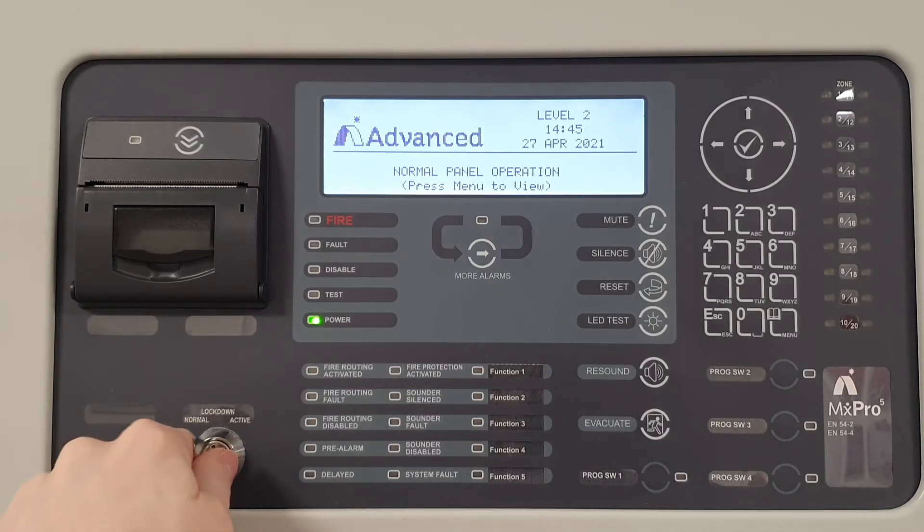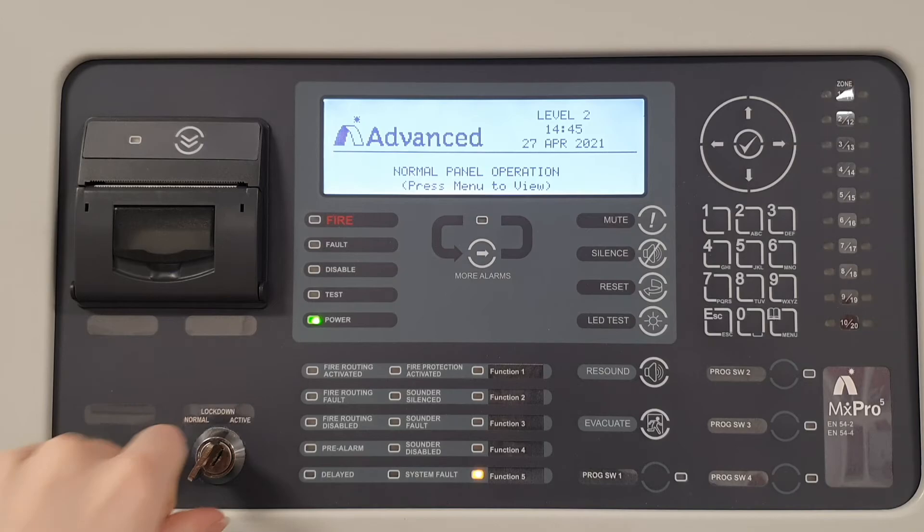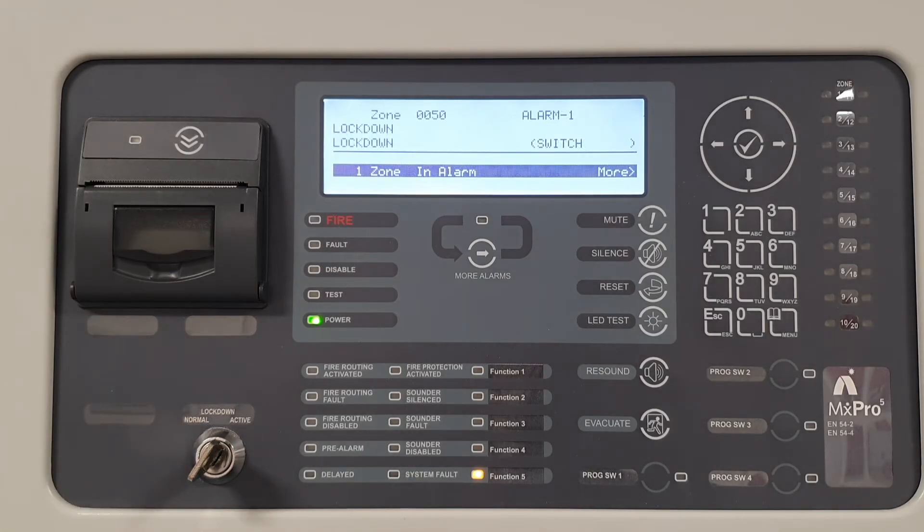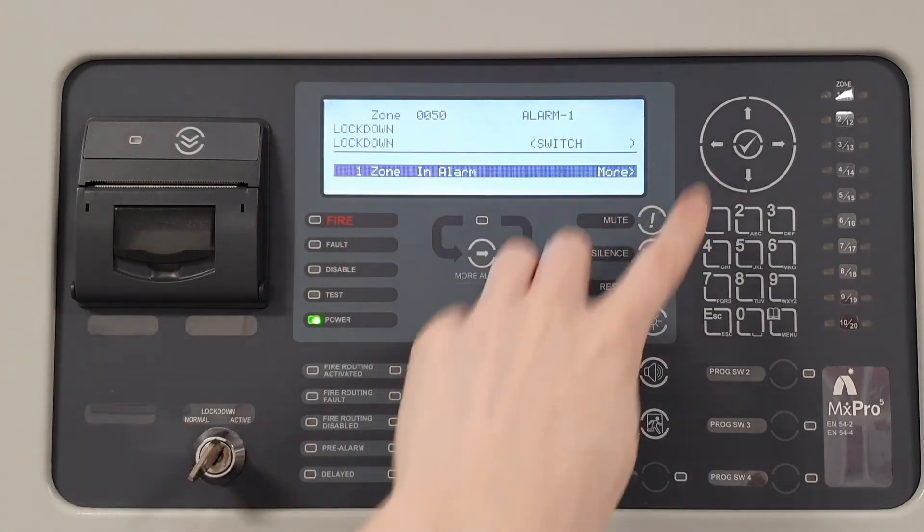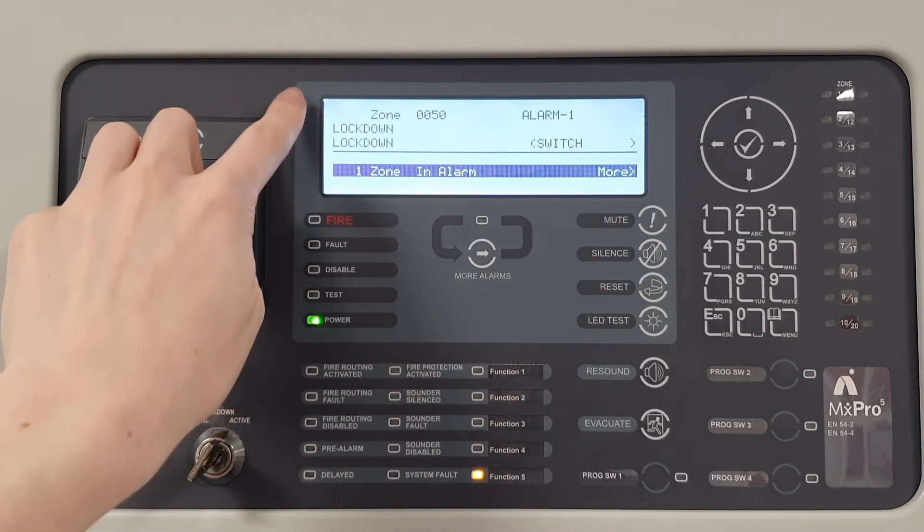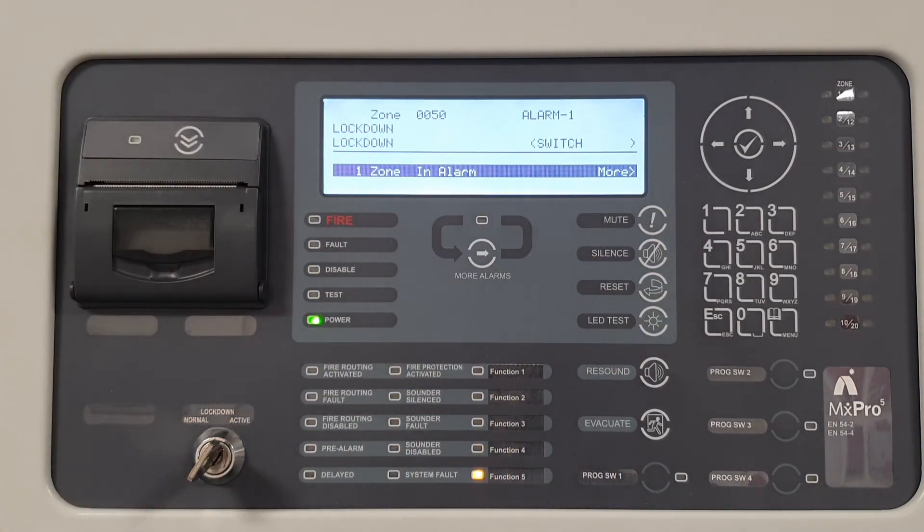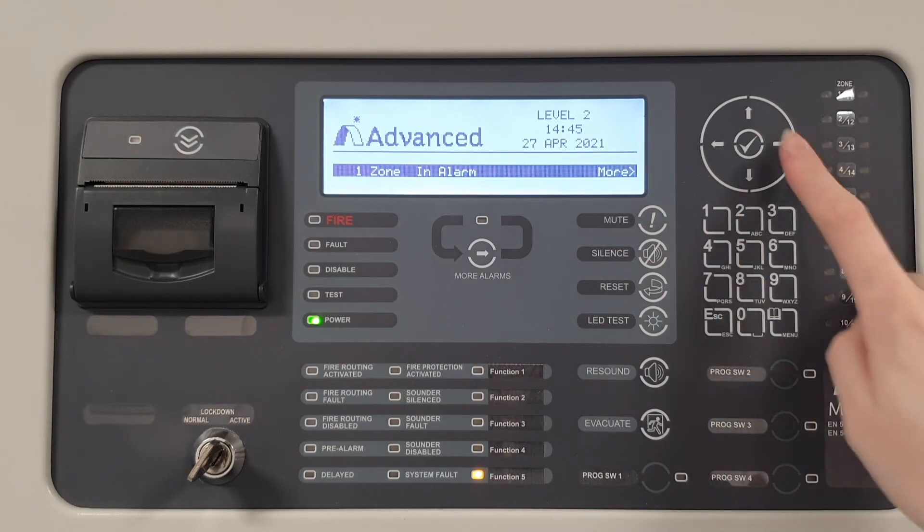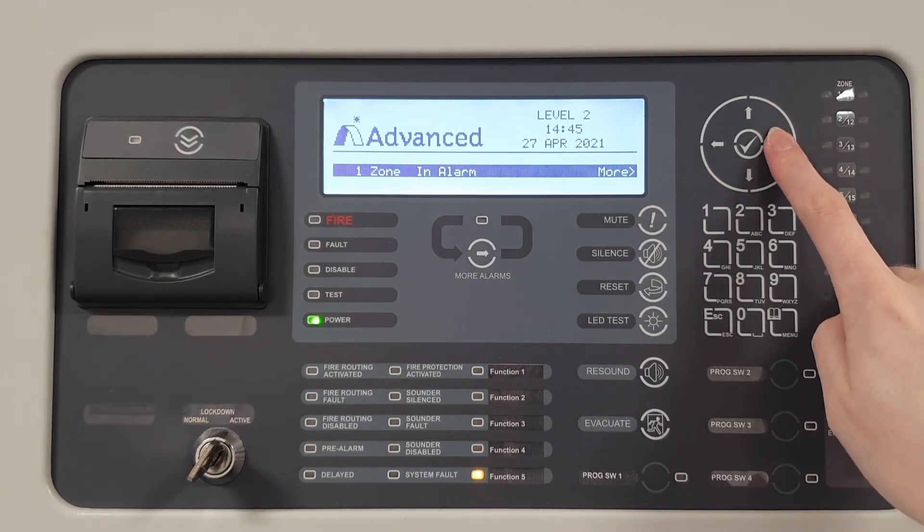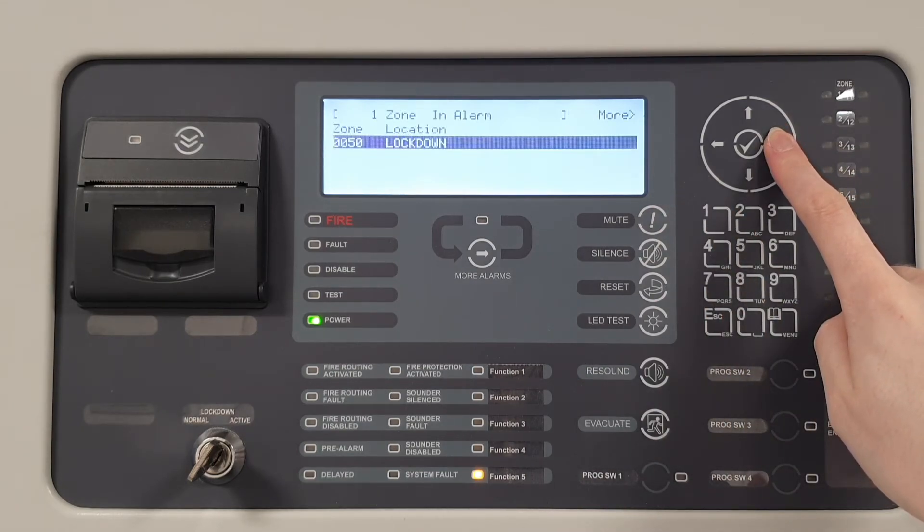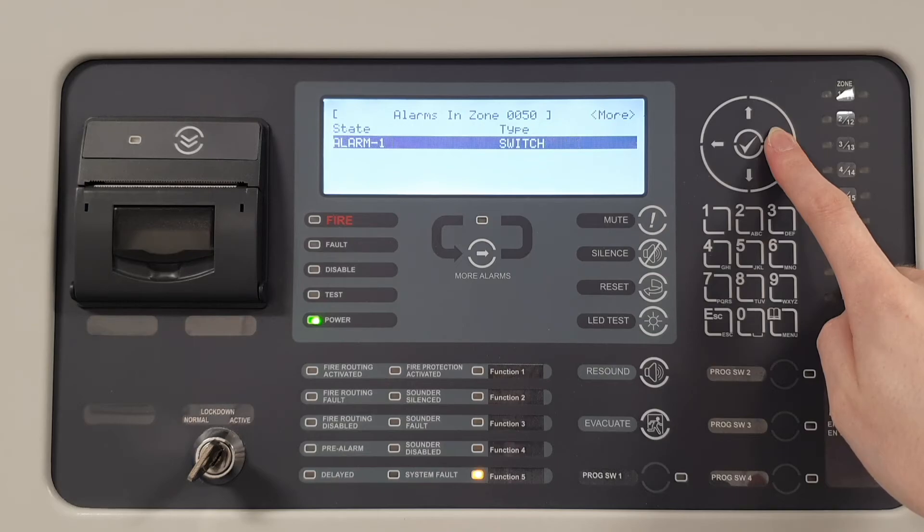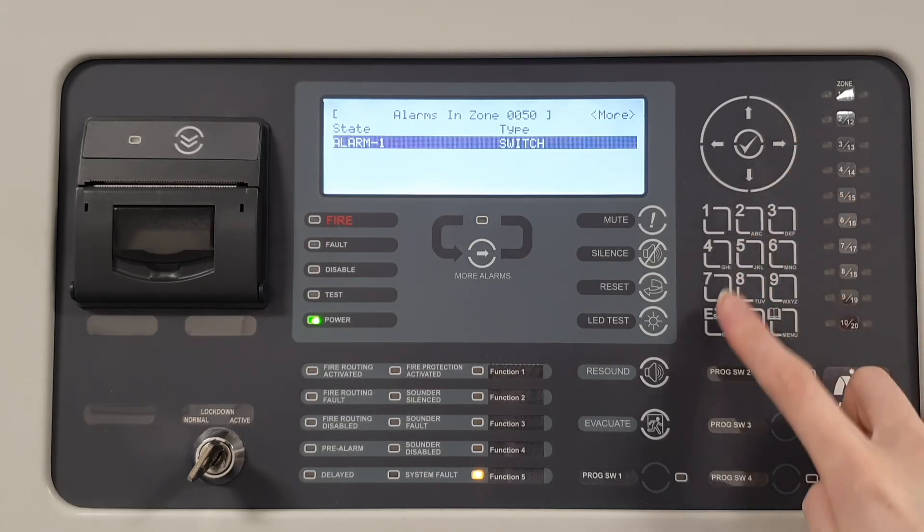When the key is turned, the LED turns on and the panel shows an alarm condition. The panel buzzer will also operate. Pressing mute will silence it. Scrolling to the right from the main menu will display more information on the activated device, such as the zone and location text.